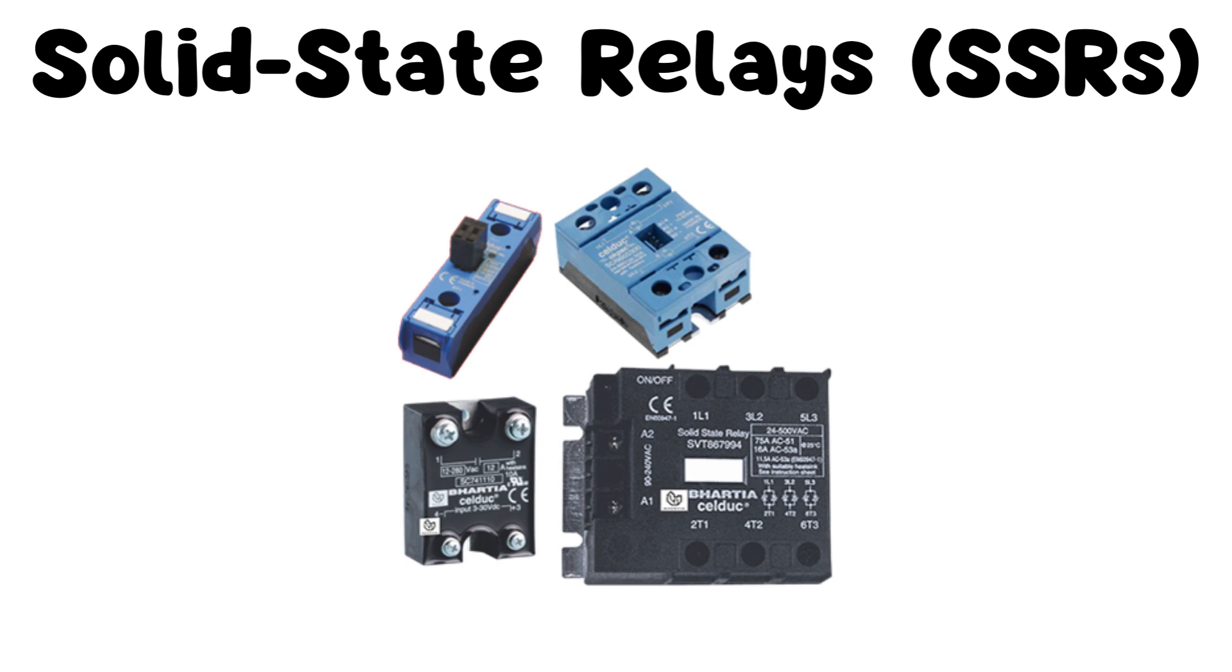Solid-State Relays (SSRs): SSRs use solid-state components like thyristors or transistors to perform the switching operation without any moving parts. They offer faster response times, higher reliability, and longer electrical life compared to electromechanical relays. SSRs are often used in applications where silent operation, high-speed switching, or resistance to mechanical wear and vibration is required.